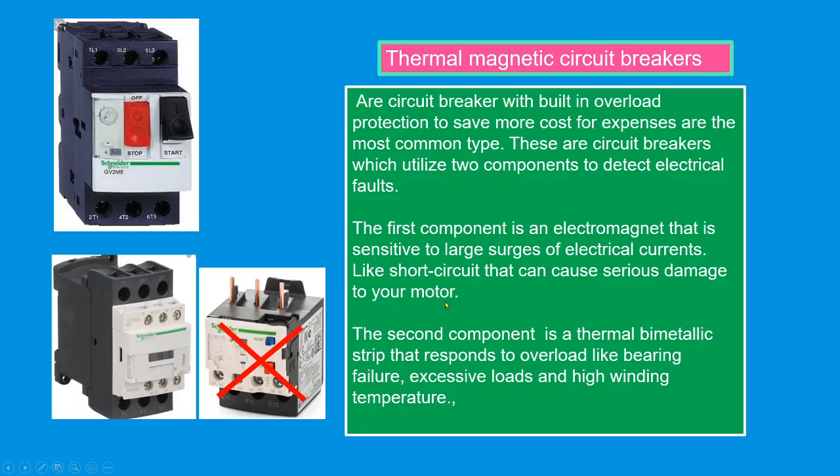Next, thermal magnetic circuit breaker. Our circuit breaker has built-in overload protection to save motor costs and is the most common type. These circuit breakers utilize two components to detect electrical faults. The first component is an electromagnet that's sensitive to large surges of electrical current, like short circuits, that can cause serious damage to your motor. The second component is the thermal bimetallic strip that responds to overload, like bearing failure, excessive load, and high winding temperature.